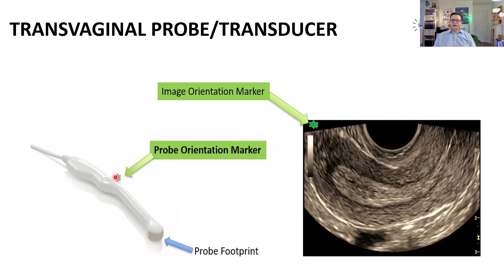So one thing that comes to mind is, how do we prepare the transvaginal transducer? We do not insert the transvaginal transducer in the patient without properly prepping it. So take ultrasound gel. It could be regular ultrasound gel. And we put a lot of gel on the footprint of the transducer. And once you see there's lots of gel, we then put a condom or a probe sheath on it, which is designed for transvaginal ultrasound. And make sure there's no air trapped over here.